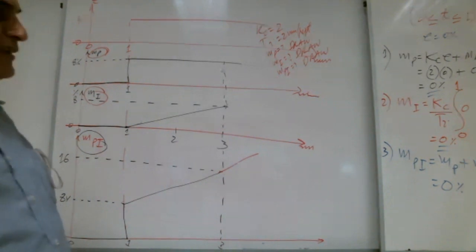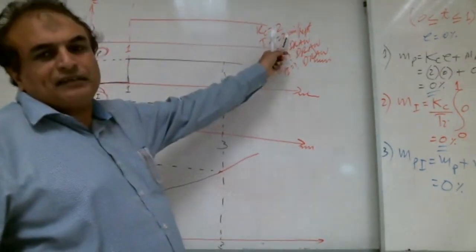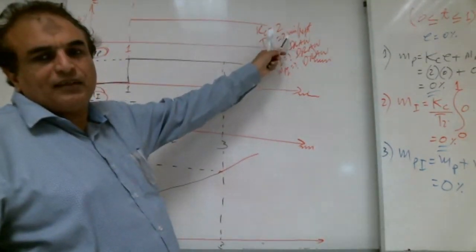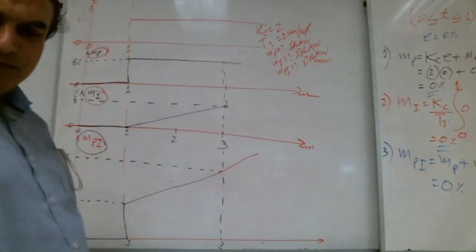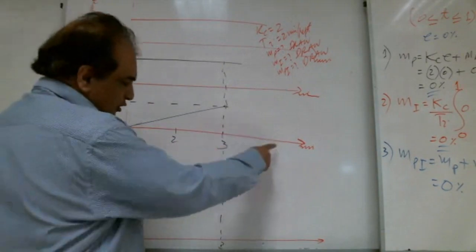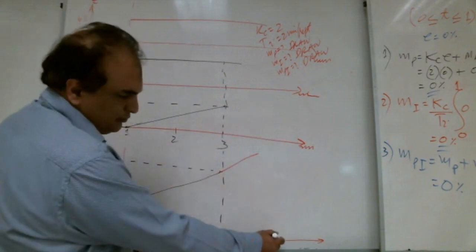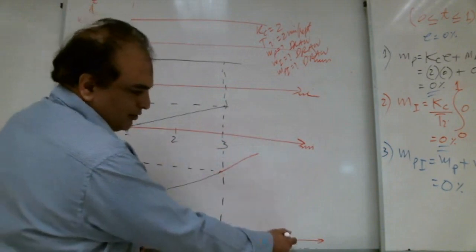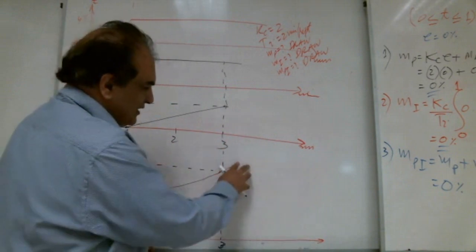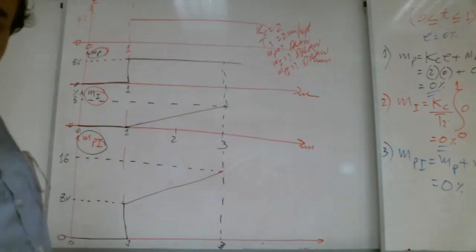No, it is not correct. Why? How much is your repeat? One repeat is 2 minutes. The integral time is 2 minutes per repeat. So if you want to increase it, you have to go up to 5, which is 3 plus 2. So my suggestion, don't go up to 5, just stop here. Right, Shabab?